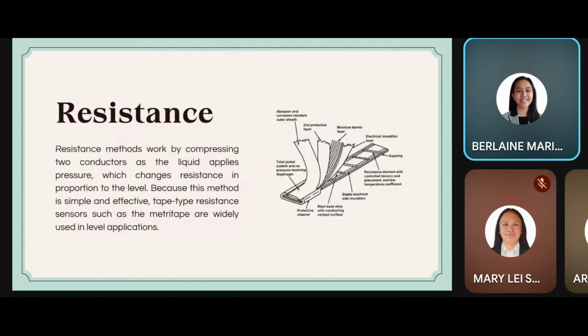Next slide, please. In the resistance method naman po, the principle is that the liquid's pressure can affect electrical resistance. As the liquid level rises, it puts pressure on two conductors placed close together. This pressure changes the electrical resistance between them. The higher the liquid level, the bigger the change in resistance. Since resistance is easy to measure electrically, it's convenient to use this method. A popular device that uses this principle is called the Metritape, which is designed for level measurement.